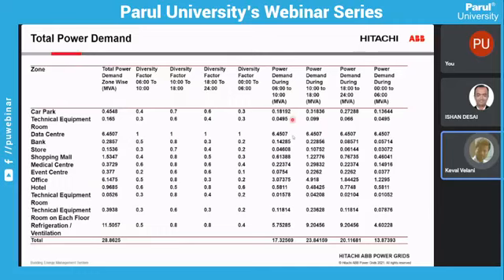Without the application of the diversity factor, the total power demand is 28 MVA. After the application of the diversity factor, you can see the decrement of the power demand. In the morning it is 17 MVA. During the afternoon condition, it is 23 MVA. During the evening, 20 MVA, and during night condition, it is 13 MVA. So this is the actual calculated power demand, and this is the operational power demand after the application of the diversity factor.